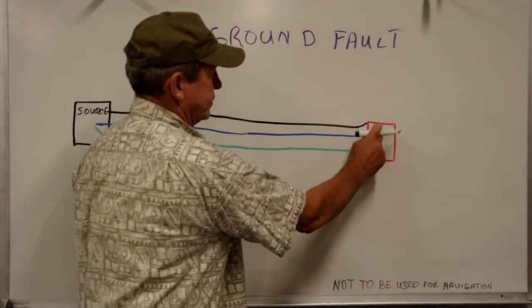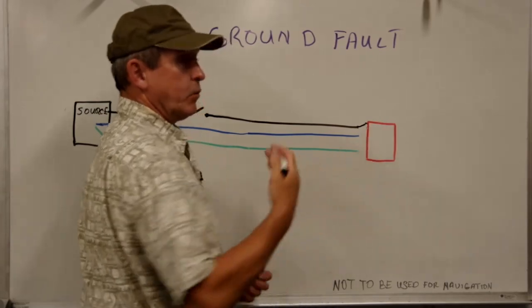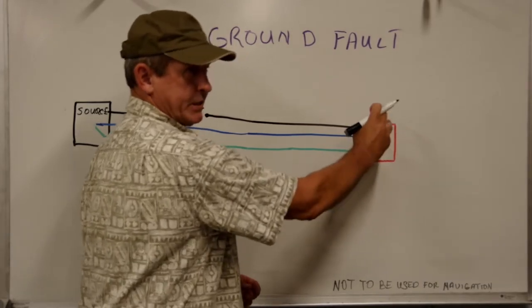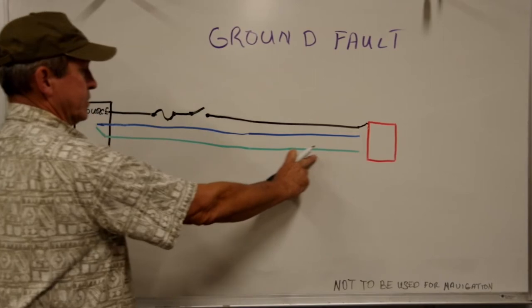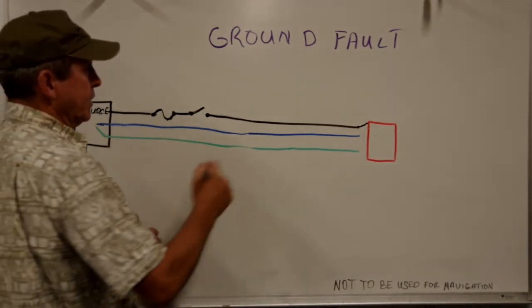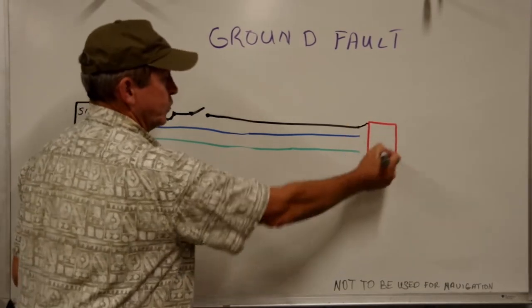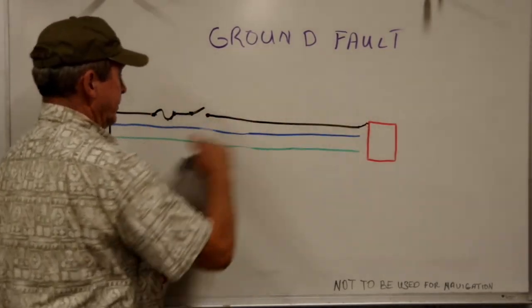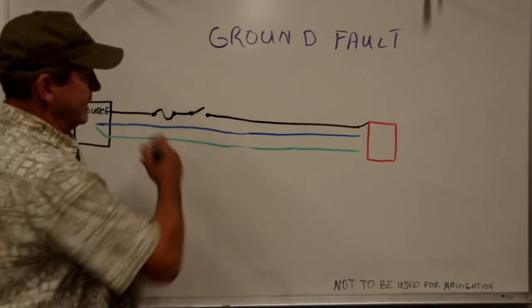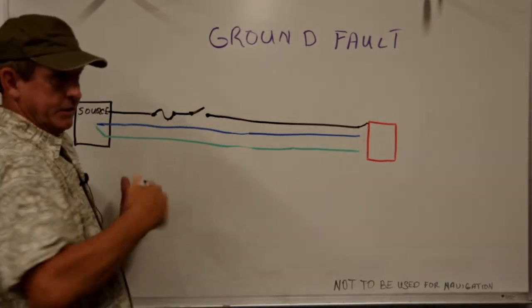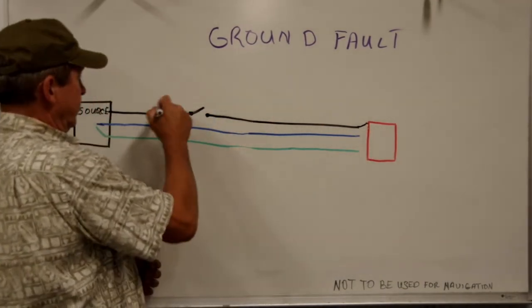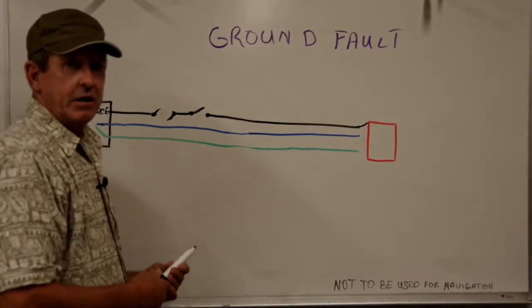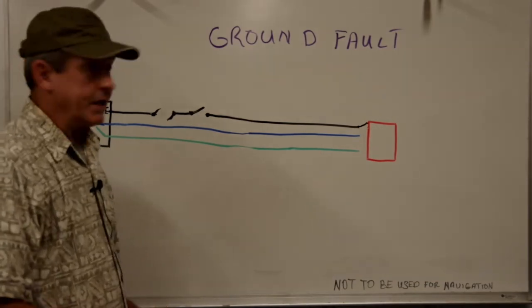What should happen is that the current energizing the chassis of our appliance can find a path back to its source along the AC safety ground. Because there's no resistance of the device between line and ground now, the current flow through here is going to exceed what we've designed this circuit to carry. So we should blow that fuse, trip that circuit breaker, turn off power — and that's how the AC safety ground should work in the case of a ground fault.